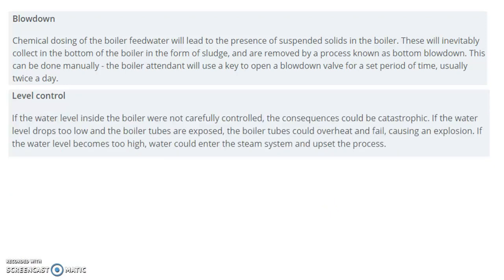Next is level control. If the water level inside the boiler were not carefully controlled, the consequences could be catastrophic. If the water level drops too low and the boiler tubes are exposed, the boiler tubes could overheat and fail, causing an explosion. If the water level becomes too high, water could enter the steam system and upset the process.